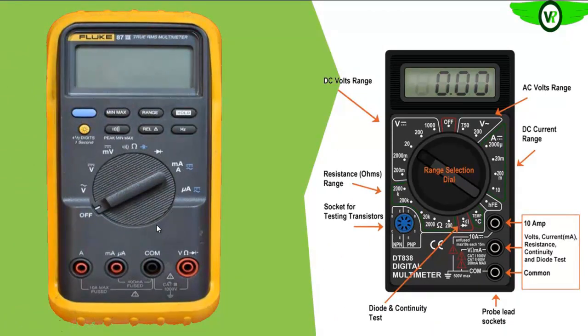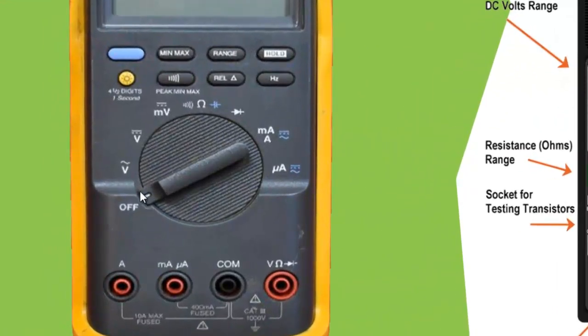The digital multimeter you see on the left of your screen is another form of digital multimeter, but if you look at it critically, you'll see there are no ranges — only the various functions. The first one here is for AC circuit testing, the other for DC circuit, millivolts test, continuity and resistance test, capacitance test, diode test, then the current tests: milliamp range, amp range, and microamp range.